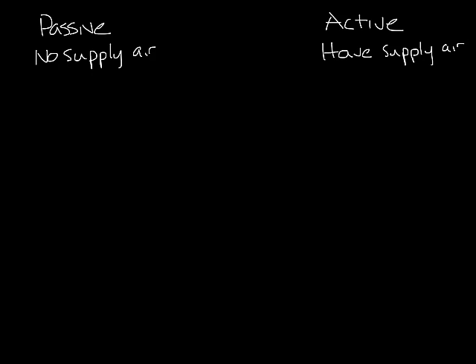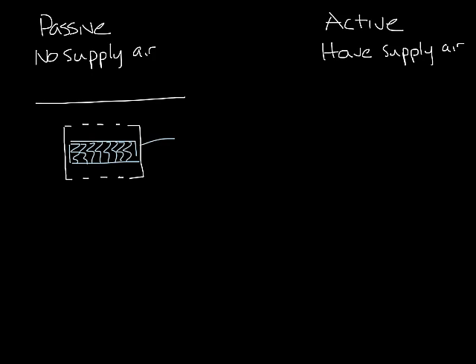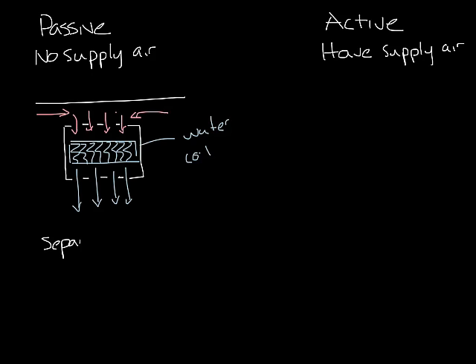So let's look at a passive chilled beam. They're always mounted below the ceiling, and they are essentially a casing around a water coil with openings in the top and bottom for air to pass through. This is our water coil right here. Now warm air in the room will rise to the ceiling. Next it'll pass into the chilled beam, through the water coil, and into the space to provide cooling. As I said, there's no supply air on a passive chilled beam, so you have to have a separate system providing ventilation air to meet your ASHRAE 62.1 requirements.